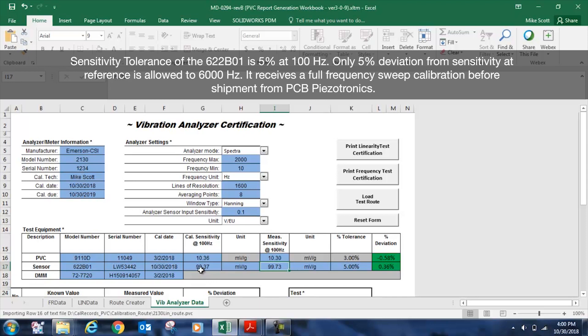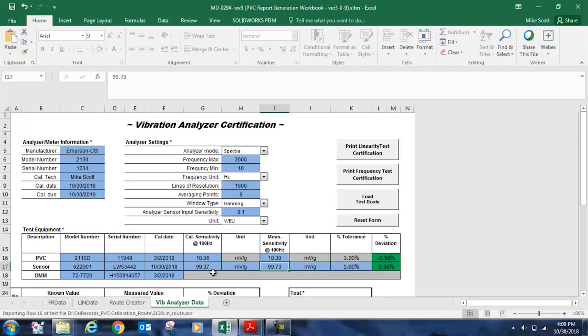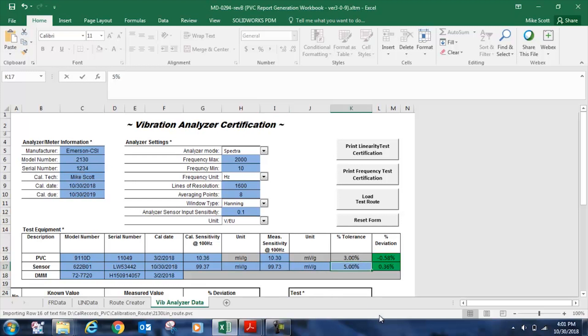So 99.37 on the day it was calibrated, and then we measured 99.73 with the 9110D, and that creates a deviation of just 0.36%. Our tolerance is 5%, as I said, for the 622B01. We can change that if we're using a sensor that has a wider tolerance.